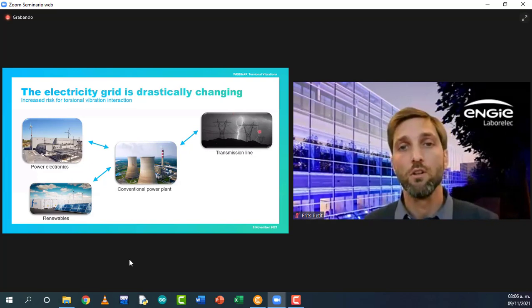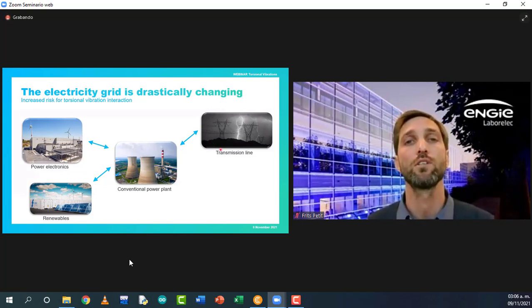We have other changes, large distance connections in between countries. For instance, here in Belgium, we have an undersea power cable, a 1 gigawatt high voltage DC connection between Belgium and the UK. Of course, when this voltage is at land, you need to convert it again from DC to AC, and there you have a converter station, an HVDC converter station, which converts the DC to AC and vice versa. Again, this is controlled in a higher frequency range, which can match with the frequency range of the torsional vibration. So again, potential interaction, and there are a large amount of these converter stations being implemented as we speak.